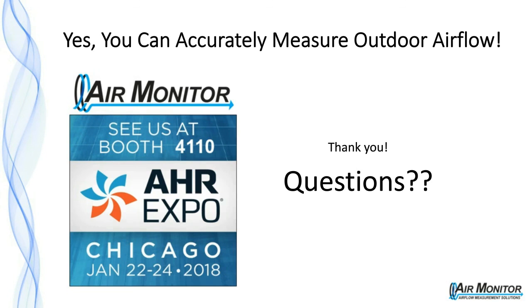Okay, the question is, are there specific louver types that this product cannot be attached to? Minimum blade spacing requirements are approximately 1/4 to 3/8 of an inch, so we really don't need a lot of spacing. It's just for the sensor to fit through and get to the other side of the louvers. We have not encountered a specific louver that we cannot apply the technology to, but it's always possible that there are some louvers out there that might be more of a challenge. If that's the case, we can introduce what we call our OAM station that has expanded metal and provides you with an adequate pressure drop that we can measure there.